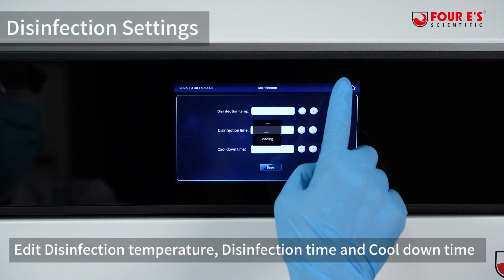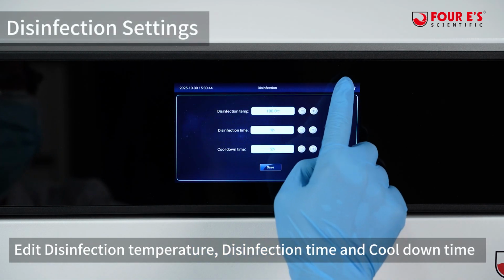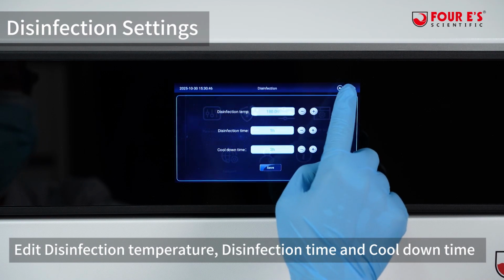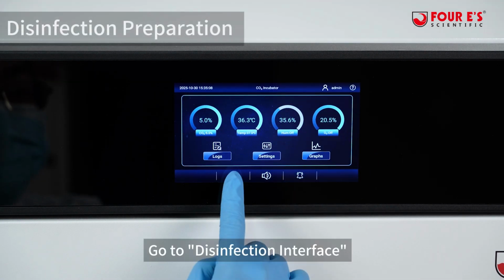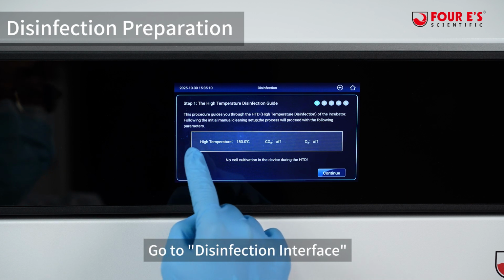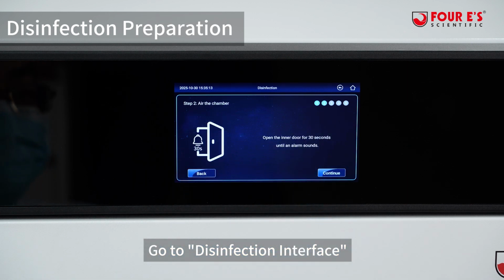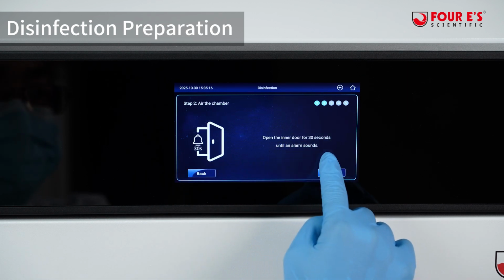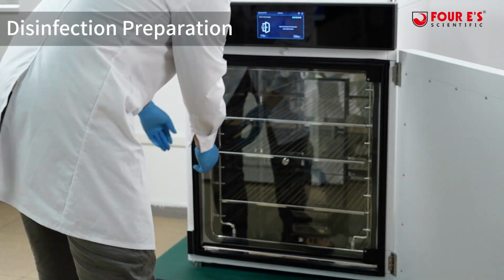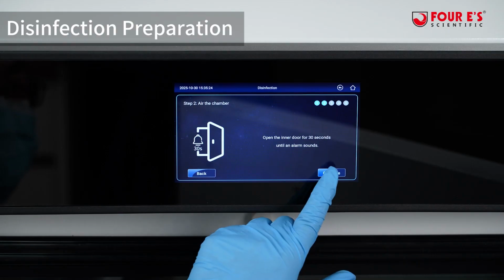Disinfection. Edit disinfection temperature, disinfection time and cool down time before starting the disinfection cycle. Go to the Disinfection interface and follow the instructions to prepare for high temperature disinfection. Open the chamber door for 30 seconds. This is to make sure the door sensor is working.